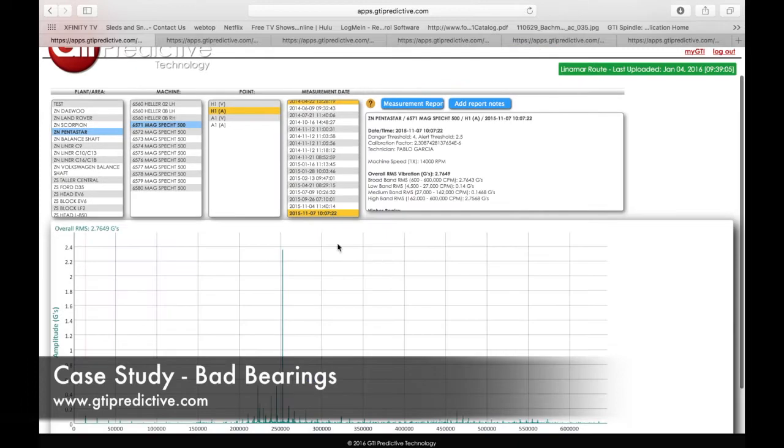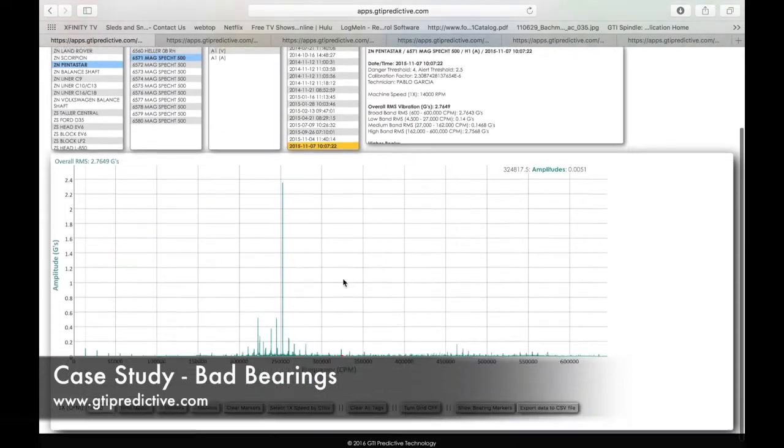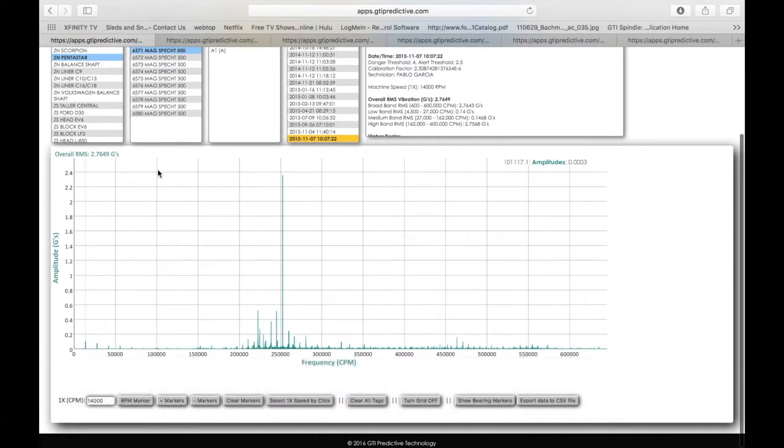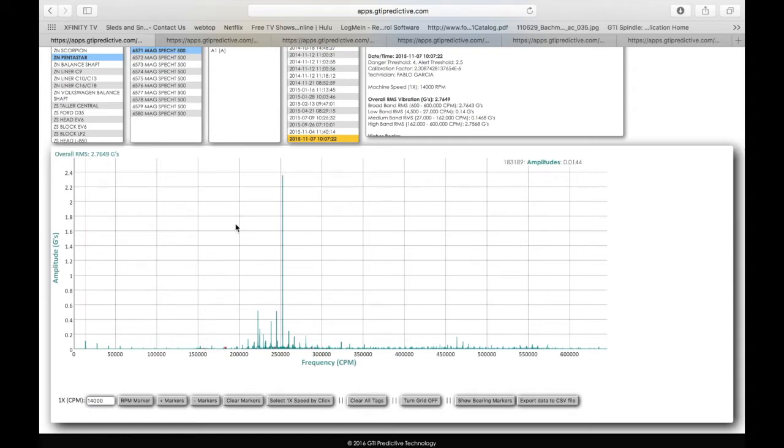So let's go back, look at the last spectrum and see if we agree with that. We're at about 2.7 Gs, which isn't—I wouldn't put it in the red either. It's not going to fail immediately, but we definitely have a bearing issue here in the high frequency domain.